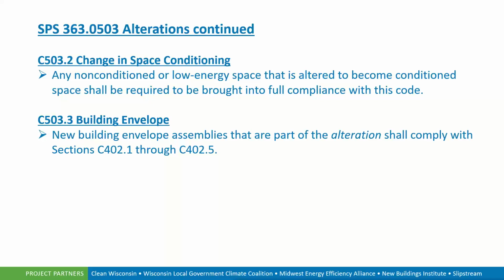We can do a change in space conditioning. Any non-conditioned or low energy space that is altered to become conditioned space is required to be brought into full compliance with the code. So everything previous in the code chapter, or previous in this presentation, would then be required for this alteration. And again, new building envelopes, as I mentioned earlier, as part of the alteration, are required to meet sections 402.1 through 402.5 for the building thermal envelope. So any new construction is required to meet those as well.